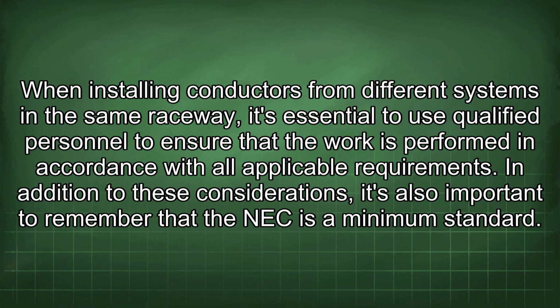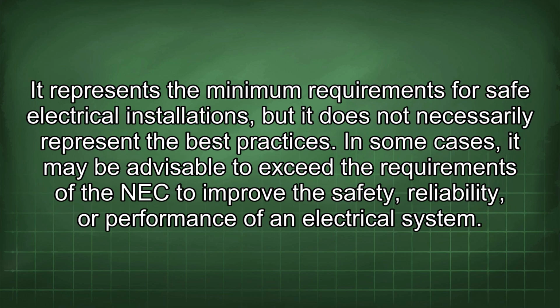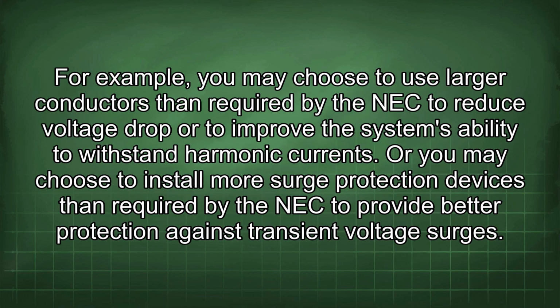In addition to these considerations, it's also important to remember that the NEC is a minimum standard. It represents the minimum requirements for safe electrical installations, but it does not necessarily represent the best practices. In some cases, it may be advisable to exceed the requirements of the NEC to improve the safety, reliability, or performance of an electrical system. For example, you may choose to use larger conductors than required by the NEC to reduce voltage drop or to improve the system's ability to withstand harmonic currents, or you may choose to install more surge protection devices than required by the NEC to provide better protection against transient voltage surges.